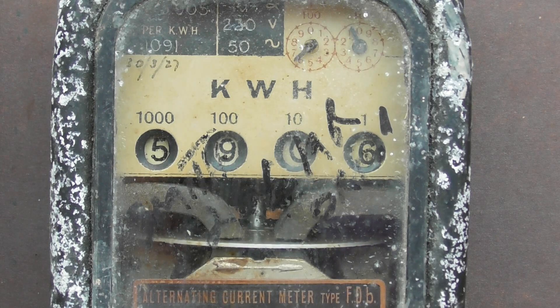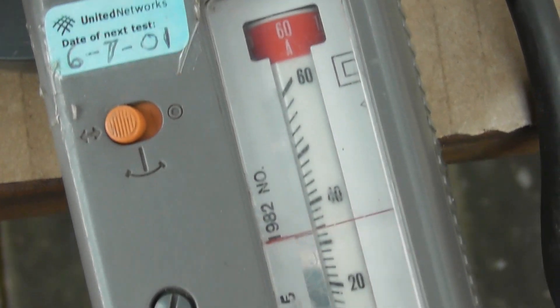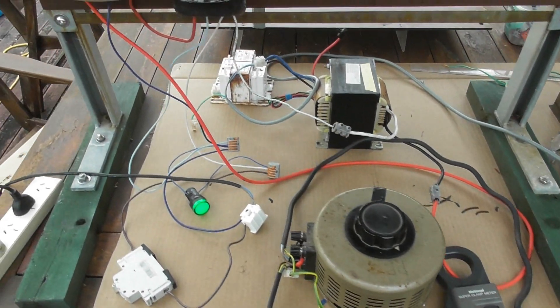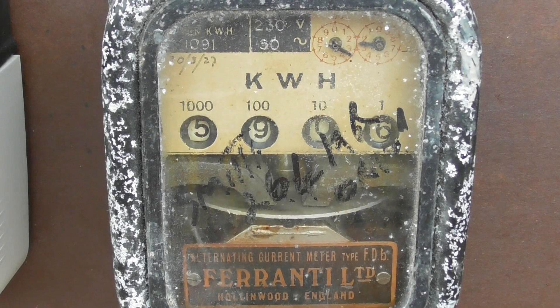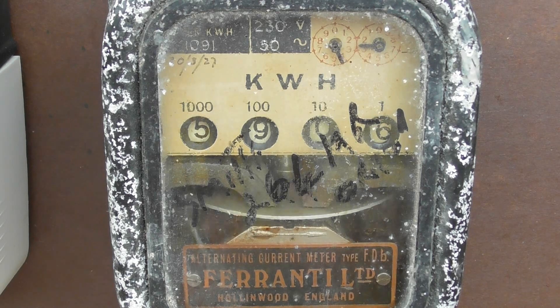The meter was hanging in there nicely. The load is about 30 to 35 ampere — that was about 33, 34 ampere. Rough setup but it works. We'll let these meters percolate for a while. The FDB, instead of having a black mark on the front of the disc, they've got a little arrow on it, so this would use the current a bit and we can see it better. So we watch the disc and we'll see there's an arrow on there.